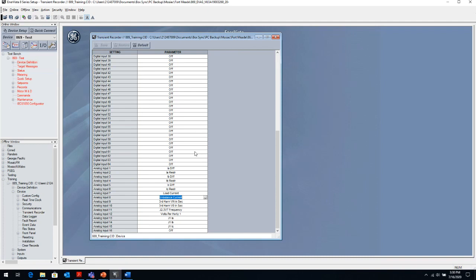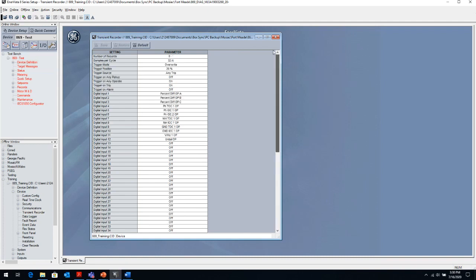So whatever you as the user want to see in the oscillography, you should come in here and program that appropriately, so that when you do have an event and there may be a problem, or not even a problem, the relay might have operated correctly, but you still want to analyze that event to see, hey, did the relay react to what I expected it to, and did it react to the power system conditions?